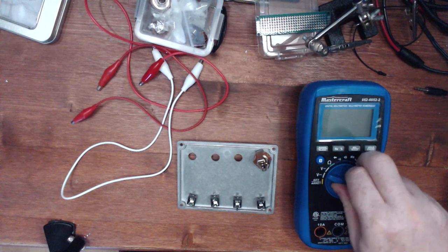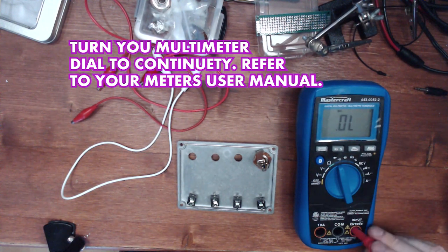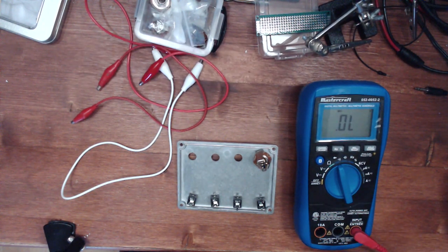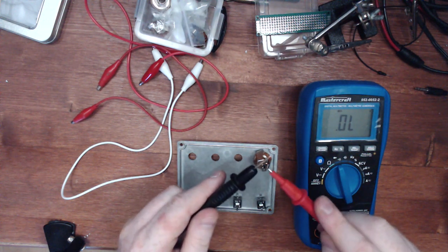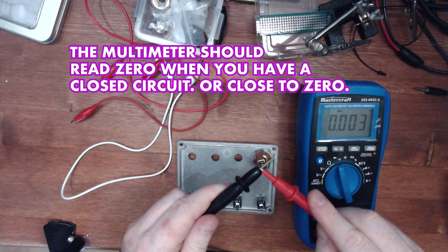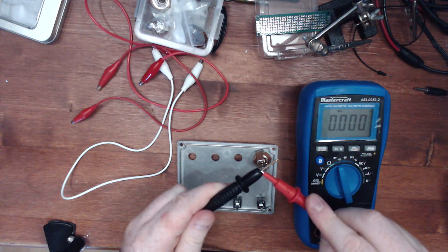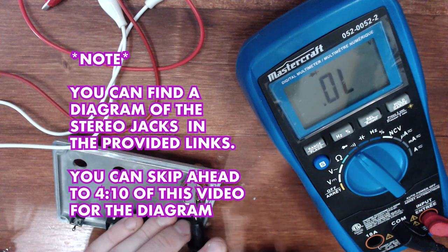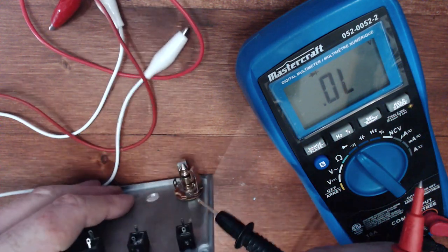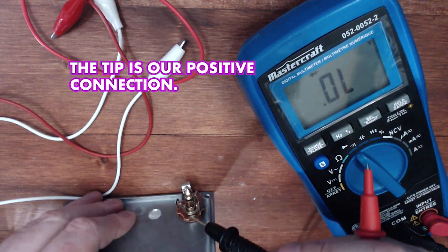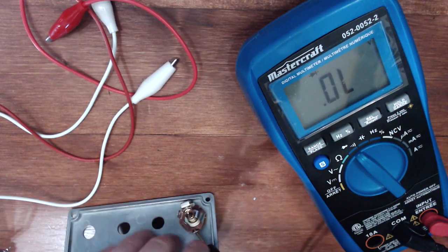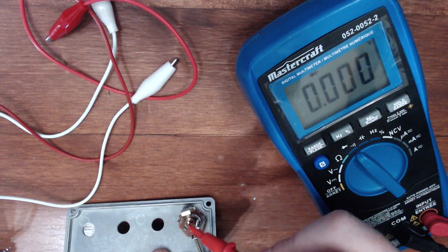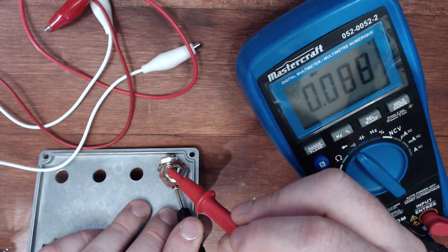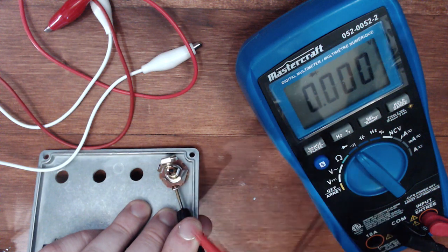Let's go ahead and test for continuity, which will determine whether we have the right connections. First, we'll test the tip connection: place one probe on the tip and the other on lug 3. If done properly, you should be getting a 0 on your multimeter.